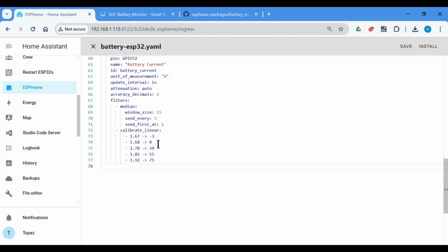So I used my multimeter, which has a clamp meter, but there are other ways to do this. I had everything disconnected, and 0 was coming in, and it was returning 1.68 on the dashboard. Then at 34 amps, it was returning 1.78, at 55 amps 1.85, and when discharging, -3 discharge was 1.67. If you get 2, 3, or 4 points, it's pretty much a linear graph, and Home Assistant ESPHome will calibrate the values for you.